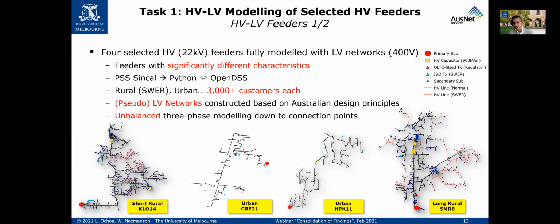So at first it might not necessarily be palatable, but what our studies are suggesting is that even with that stricter limit, combined with a volt-var, of course, both have to be there, the added curtailment that we quantify with all these 4 feeders in total, with between 12 and 15,000 customers, is that the added curtailment on average is just 1% more. So it's not really that significant.